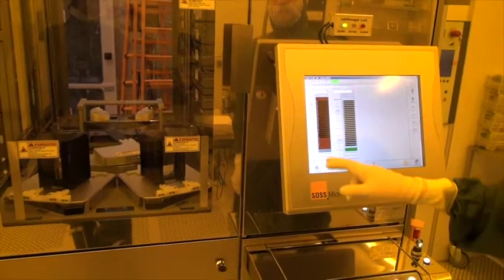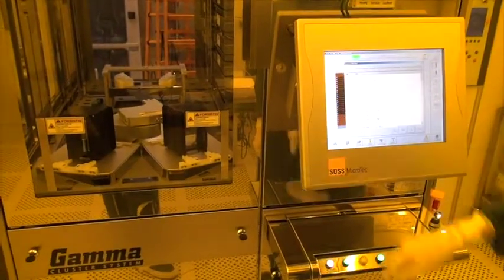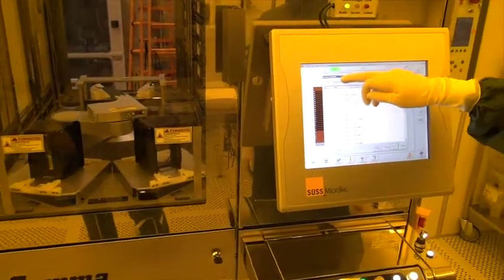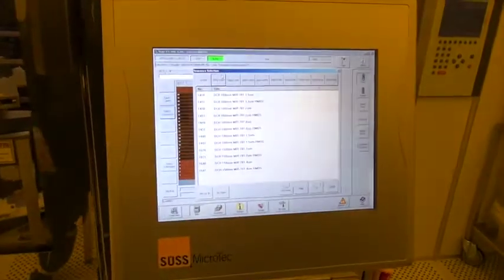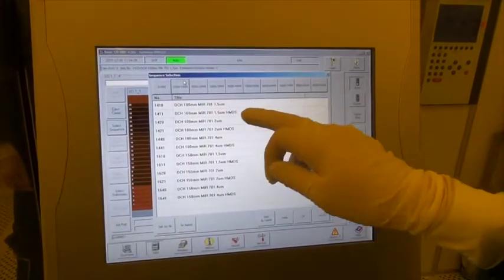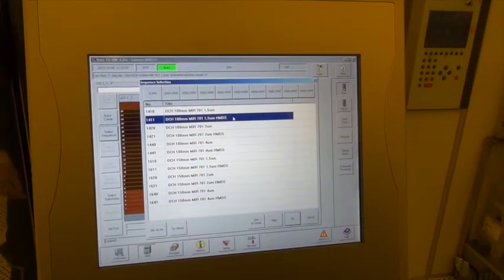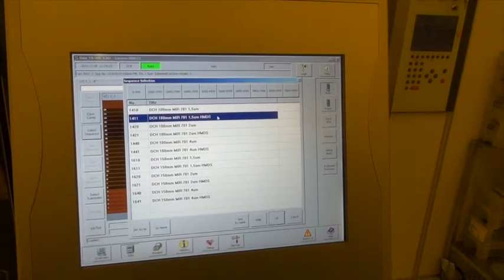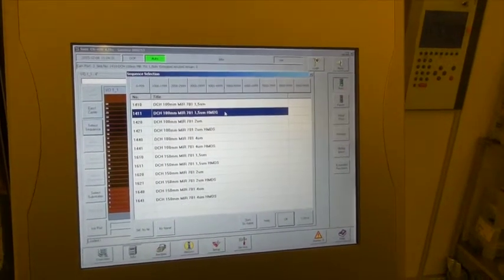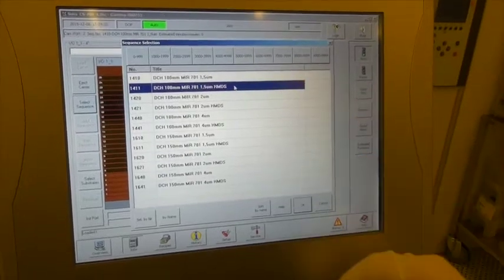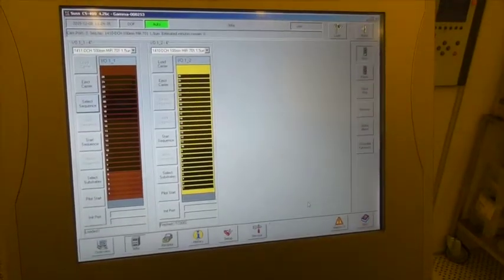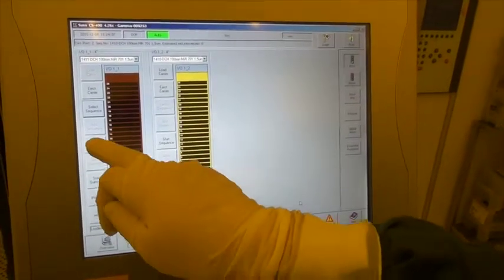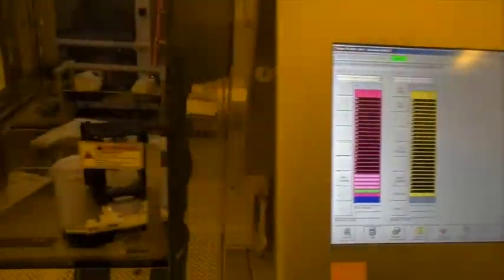And while it is loading I can select my sequence. Again select the MIR sequences and this time I want HMDS priming on my wafers. So I select a sequence that has HMDS in it. Press OK and press start sequence to start processing.